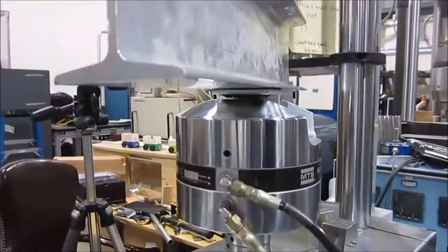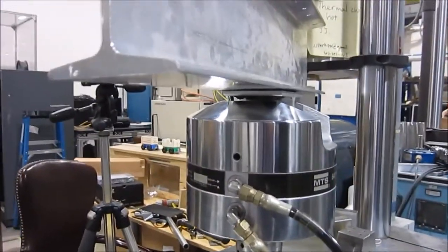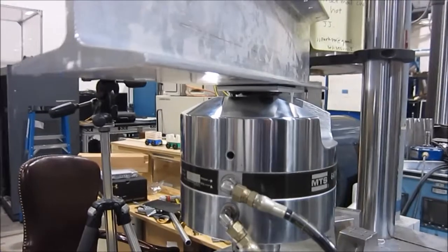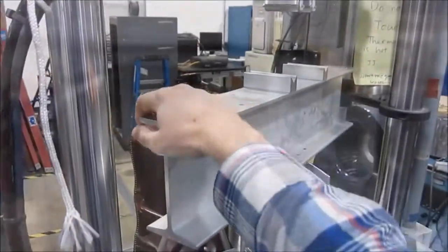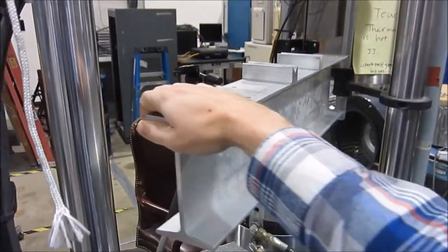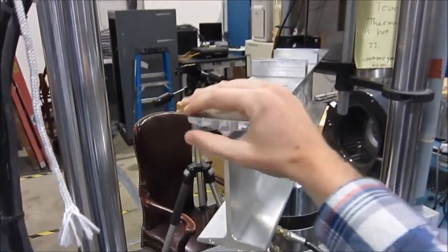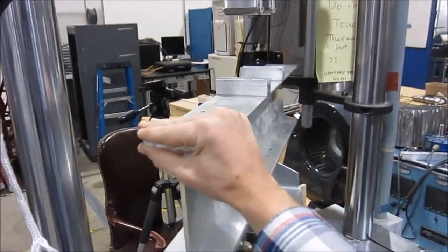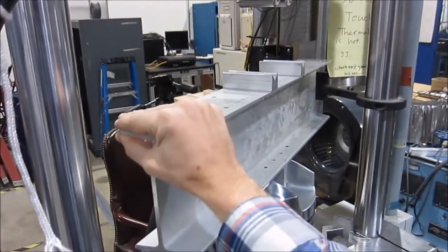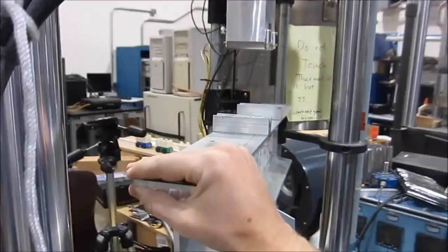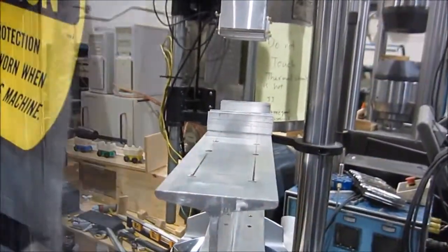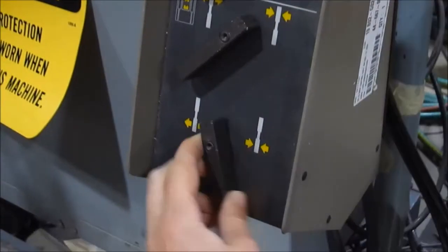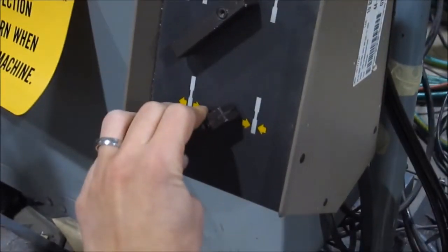Again, these are very powerful things, so don't get your fingers caught in them. Be sure you have your test fixtures aligned properly before you insert them or before you grip onto them. The lower piston rotates so that you can do final alignment of your fixture.